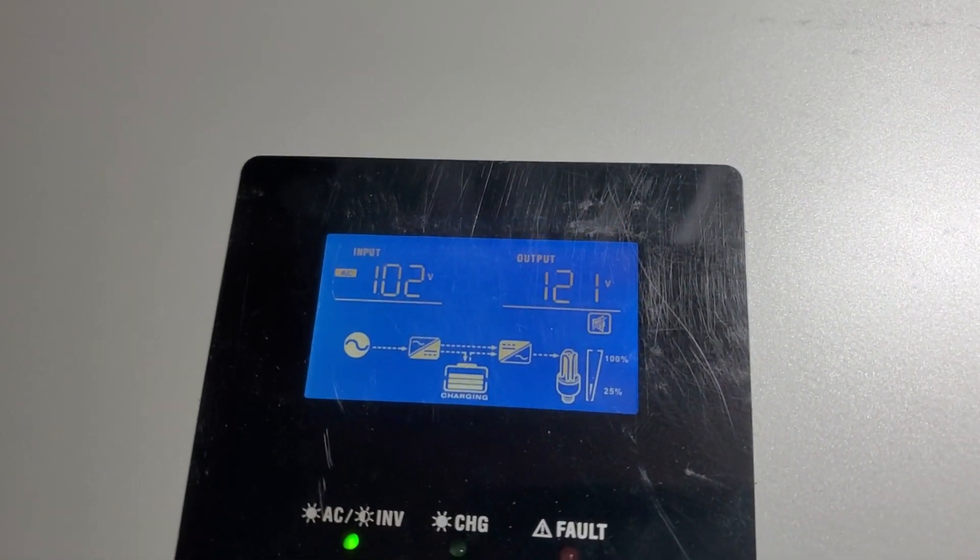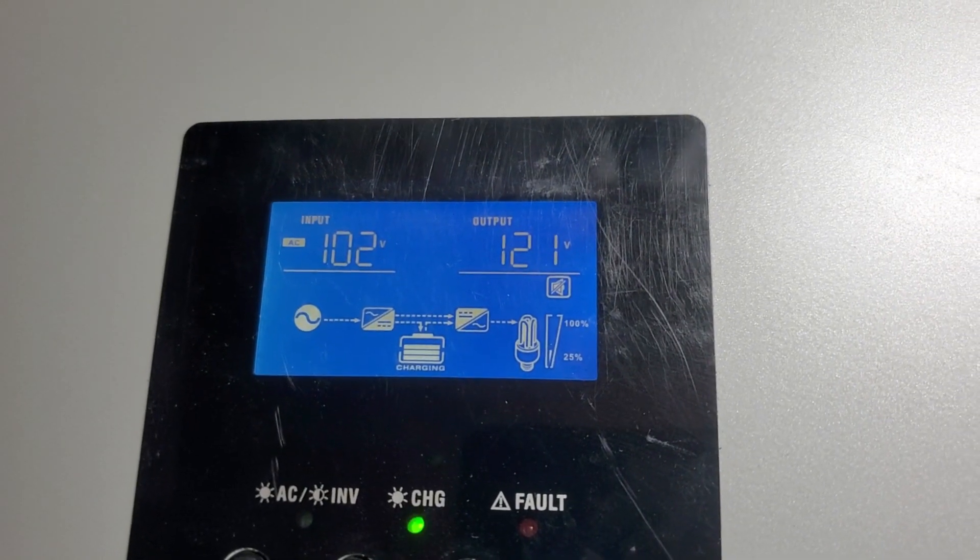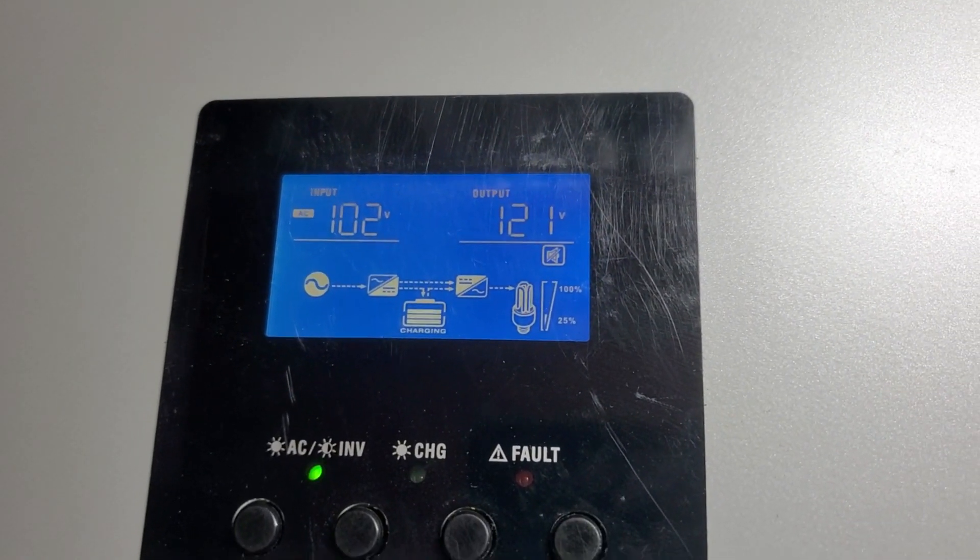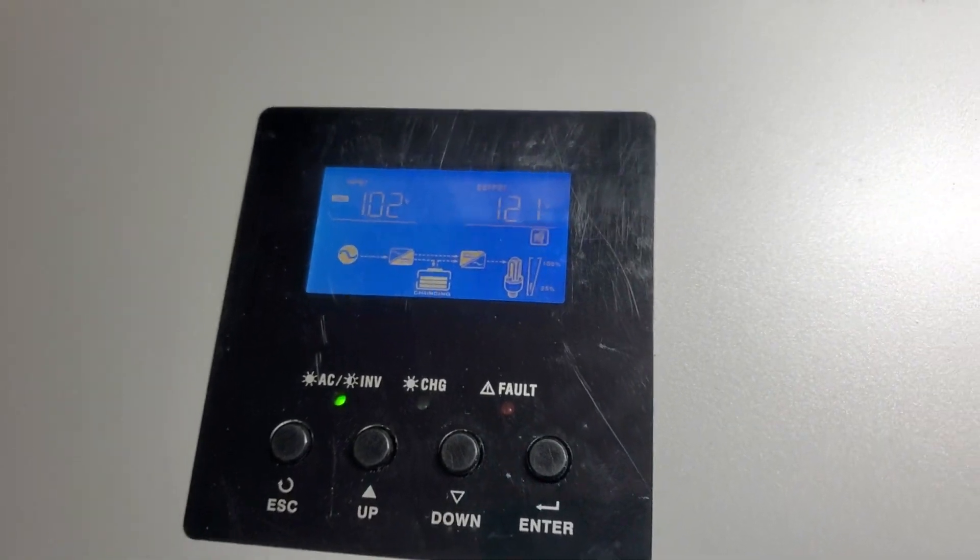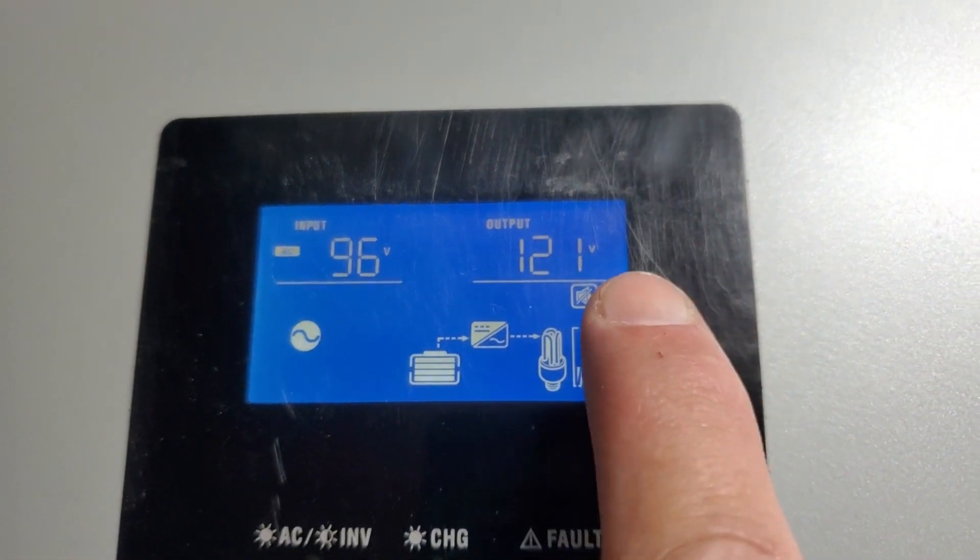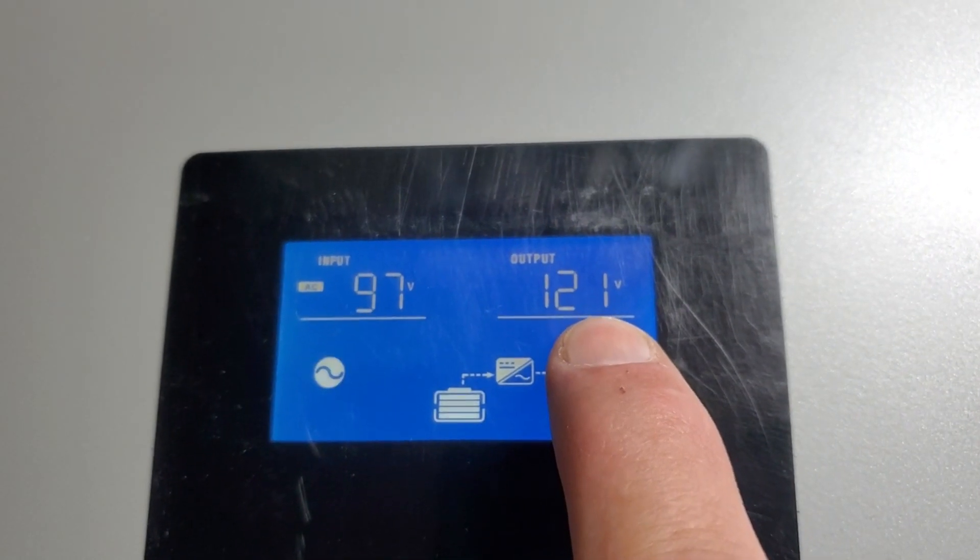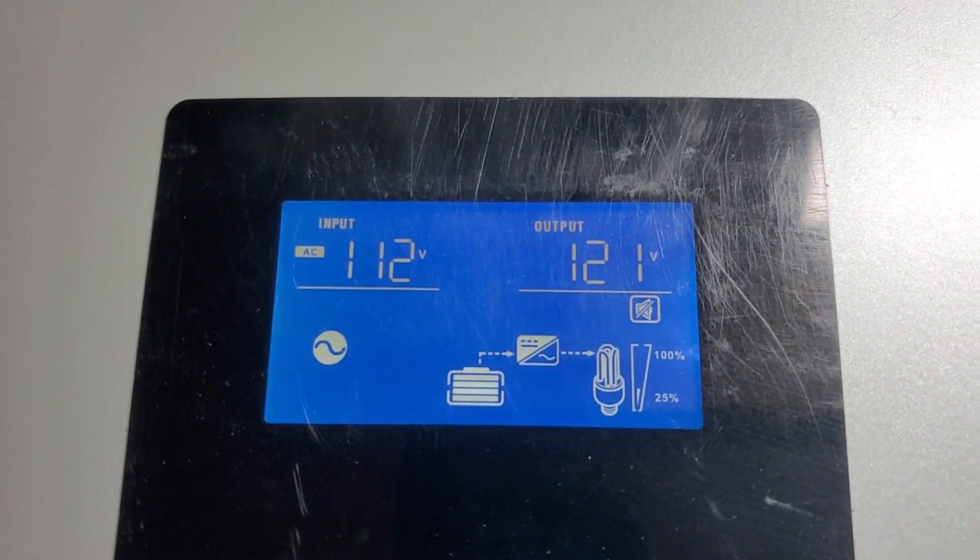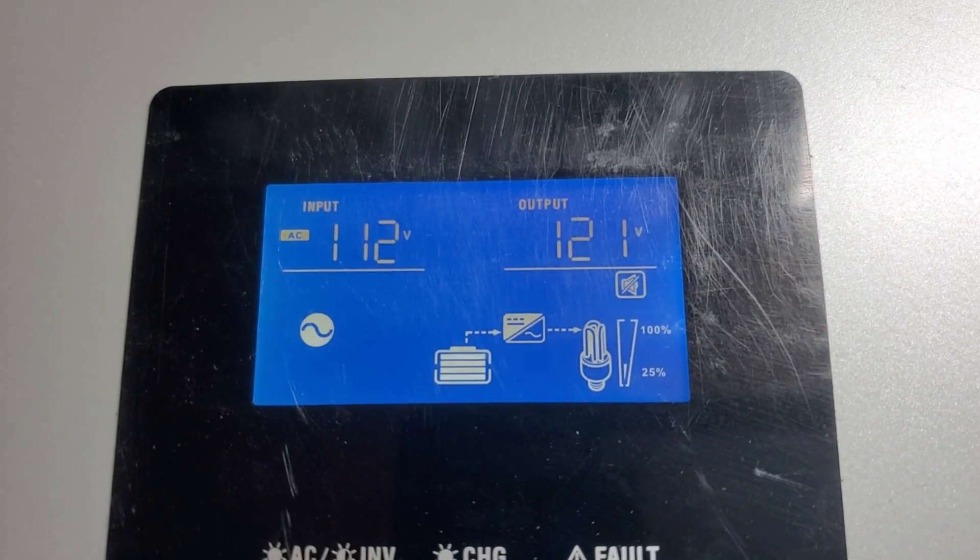So this is perfect for miners, etc., where you don't want any downtime for CPU glitches. So what we're going to do is vary the input voltage over there. And you'll notice that as we vary the input voltage, let's take it even down some more and up some more, the output always stays at 120V. All right, so we have 96V now. It didn't detect. Leave it at 96V for a little while.